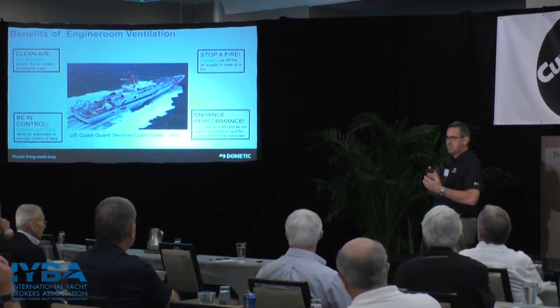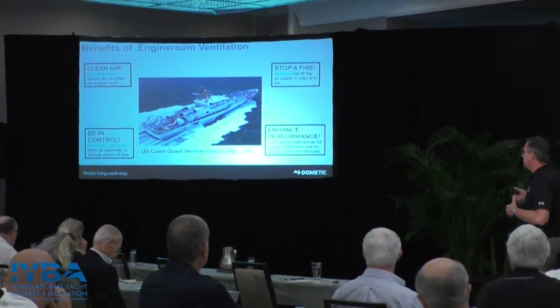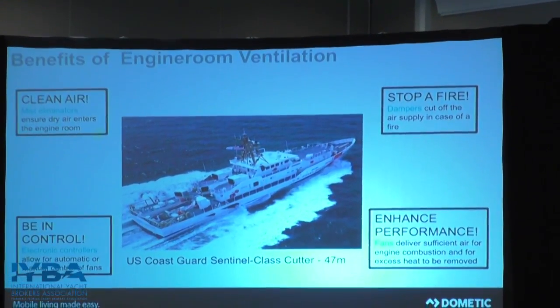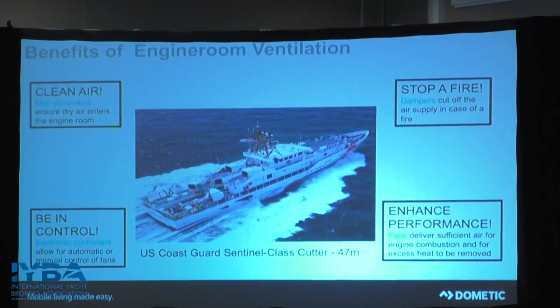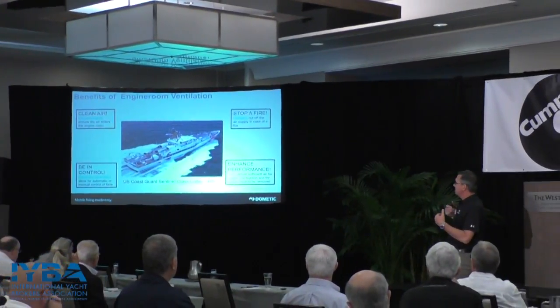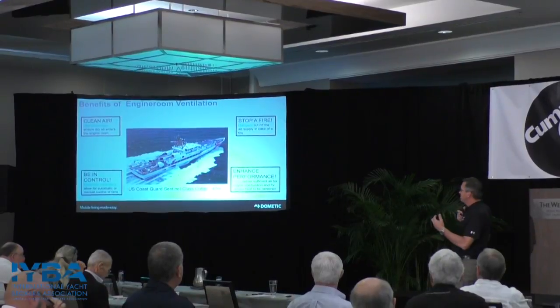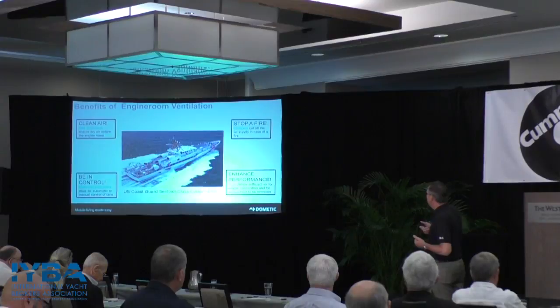Benefits of engineroom ventilation: one is clean air. You have to have engineroom ventilation — you need square opening vents to bring air into the engine room and air out. One opening is for combustion air, and another is for removing heat. We also use mist eliminators that are put into these vent areas to keep the air dry — it's a filter that removes water from the air so the air coming into the engine room is dry.